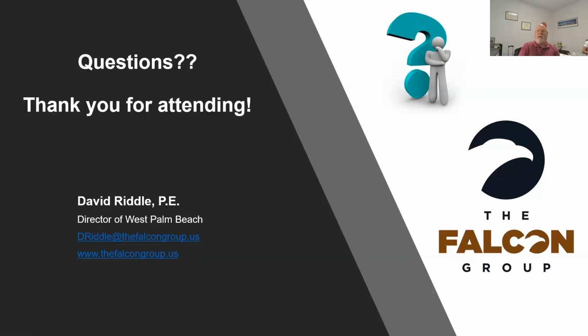One of the big things, and again, stay tuned, presentation for another day: preventative maintenance is really key to maintaining and extending the life of your equipment. So if you're doing things like replacing the fills periodically, making sure that the water going into it is of high quality, that kind of high-end preventative maintenance, the tower is going to tend to last a little bit longer. But I would plan right around that 20-year time frame.